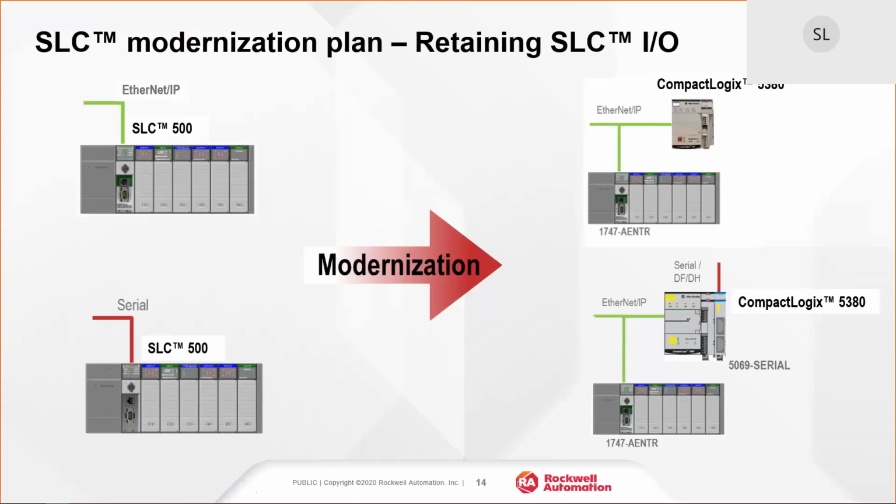Same thing happens with the SLC when you were using the serial port. None of the CompactLogix or ControlLogix processors that we have right now have a serial port. All of them have a USB port, but that is only for programming. So if you need a serial port, we do have a serial module for the CompactLogix that can be used.